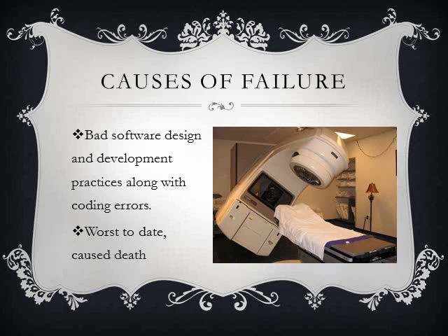The AECL had never tested the THERAC 25 with the combination of software and hardware until it was assembled at the hospital. So the last bullet is really important to see, that the AECL did not combine the hardware and the software until it was actually assembled at the hospital, where after this long process, they wouldn't want to realize that there was a failure or a flaw in the system and go back after they had worked so hard. So it's just really bad to see that they didn't test this before actually assembling it to be used for the patients.